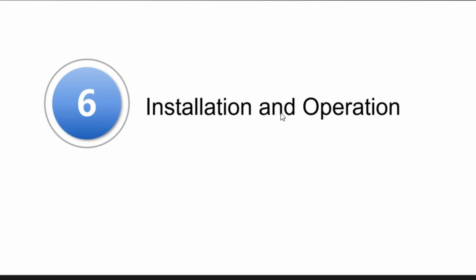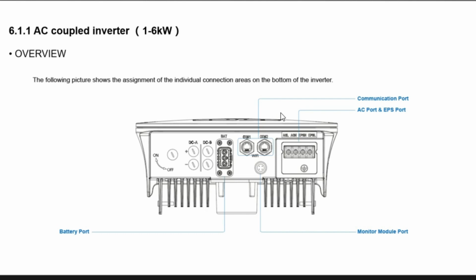I'm going to go through initially how to install a single phase hybrid inverter, and then we'll go through how to install a three-phase hybrid inverter. This is an AC coupled system. You can see on the bottom there are no PV inputs. The battery input goes in here. We don't generally use COM1, we only use COM2, and I'll show you on the hybrid in a moment what those connections are and why.